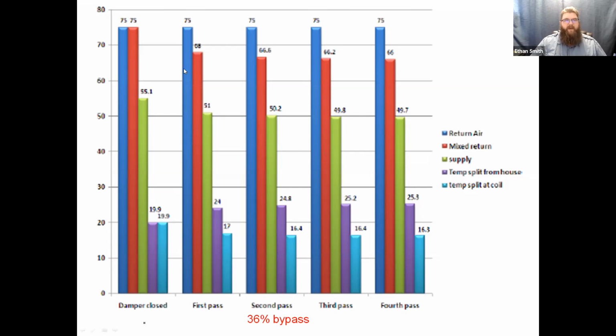On my first pass, you notice that my mixed air temperature drops because we open up that supply damper. It bypasses into my return and mixes with my return. My return has now dropped to 68 degrees. This in turn drops my supply temperature to 51. My temperature split at the house, so at the register, is 24 degrees now, but my temperature split across the coil is 17. And this trend continues.